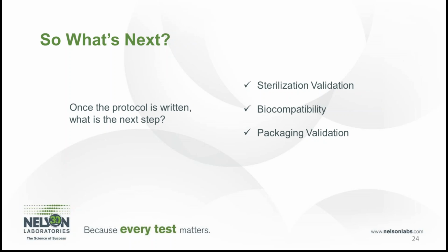Though the list of required biocompatibility tests will fluctuate depending on the device and its use, cytotoxicity, sensitization, and irritation are the three basic tests that every medical device that comes in contact with the patient has to go through. In many situations, the biocompatibility and the package validation portions can be performed concurrently, which will help reduce the overall project time to market.